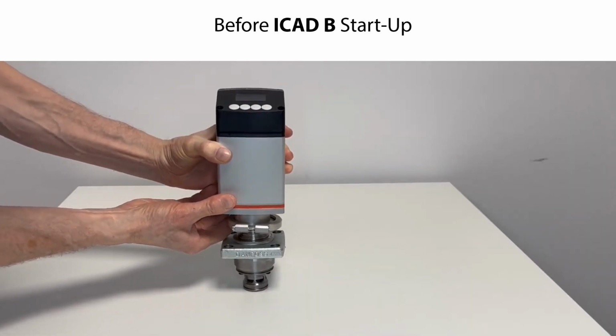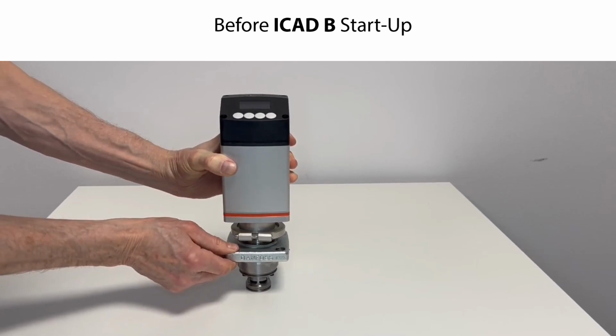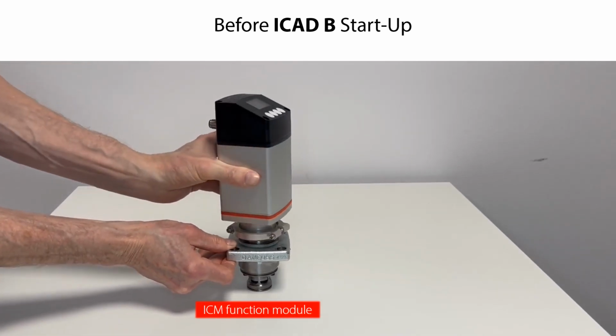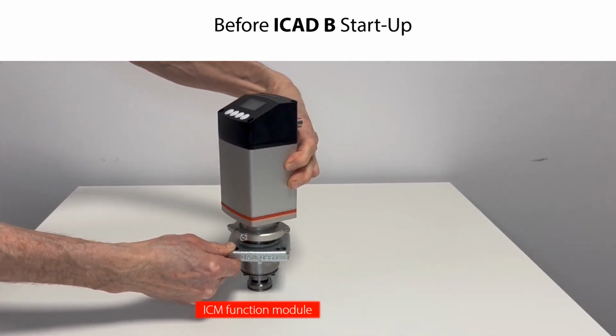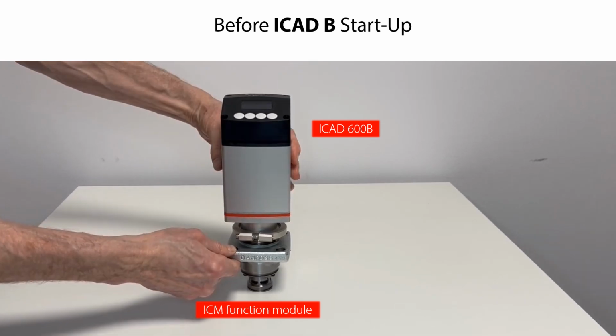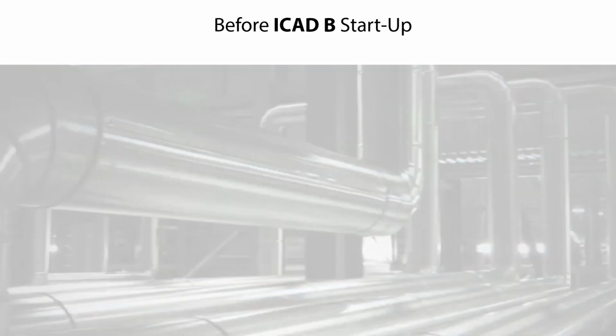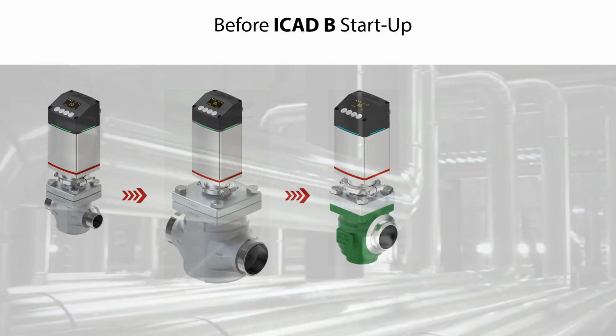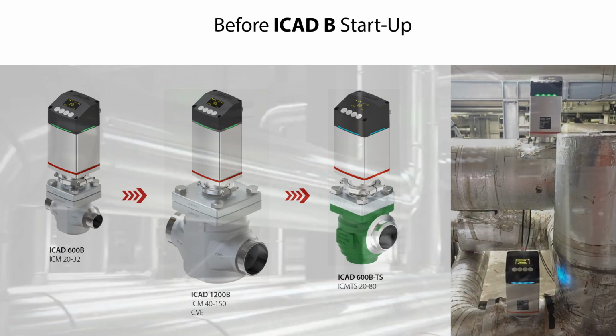In this video, we demonstrate the ICAD B setup and configuration using an ICM function module located on a table, as seen here, and we mount the ICAD 600B model with built-in display onto this ICM function module. However, the setup and configuration procedure is the same for all ICAD B models with built-in display and all suitable valves, and the setup and configuration procedure is the same with a suitable valve already located in a refrigeration system. So let us start using the display interface.